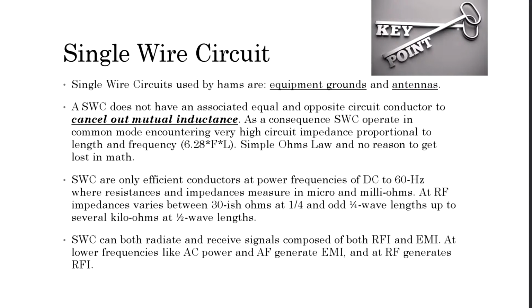Okay, a key takeaway point, and something we've been talking about for the past few minutes: single wire circuits that we use are for equipment grounds and antennas only. A single wire circuit does not have an associated circuit conductor run with it to cancel out the mutual inductance. As a consequence, single wire circuits operate in common mode, encountering very high circuit impedances proportional to the length and frequency of the conductor. Okay, it's simple Ohm's law. No reason to get lost in the math. We all know that 6.28 times the frequency times the inductance equals the impedance. The longer the wire, the more the inductance there is in the wire.